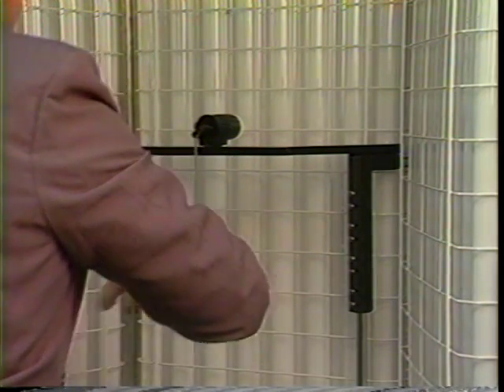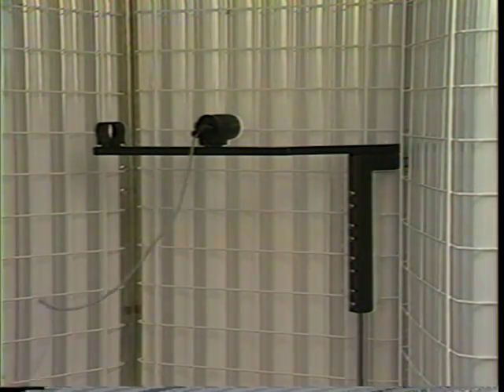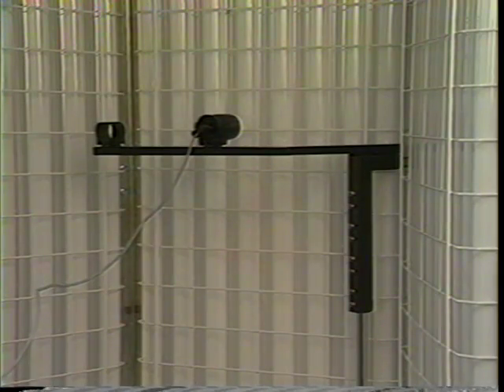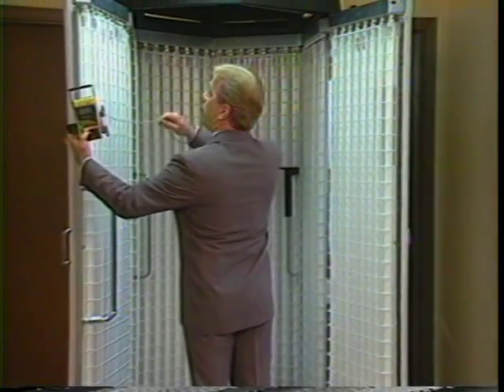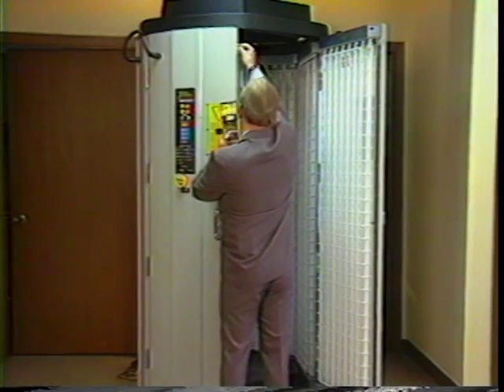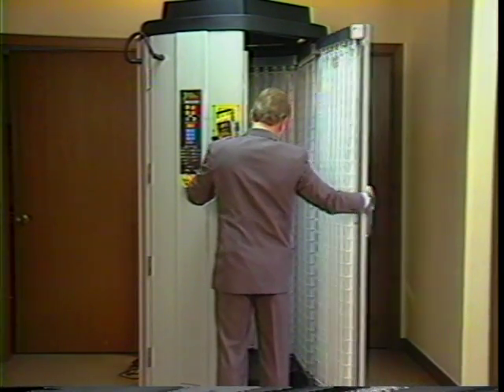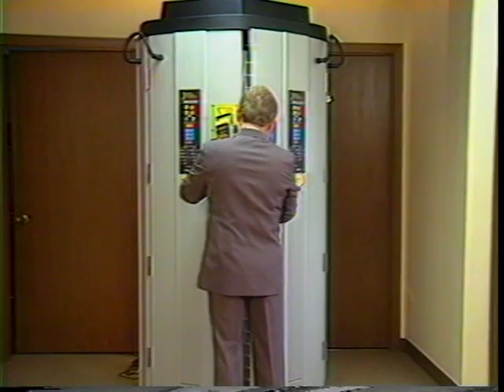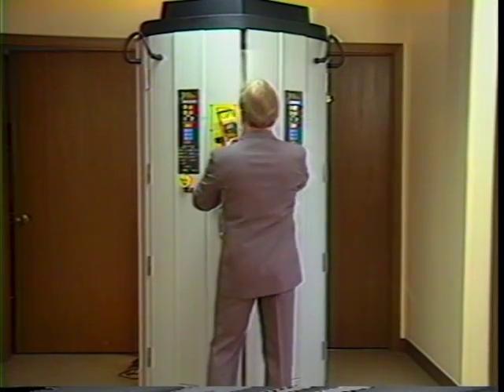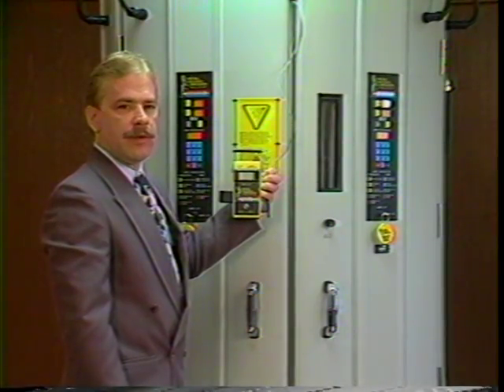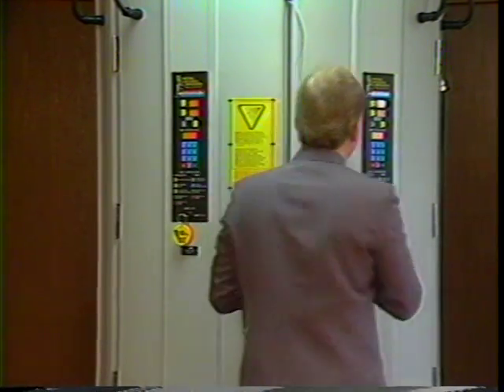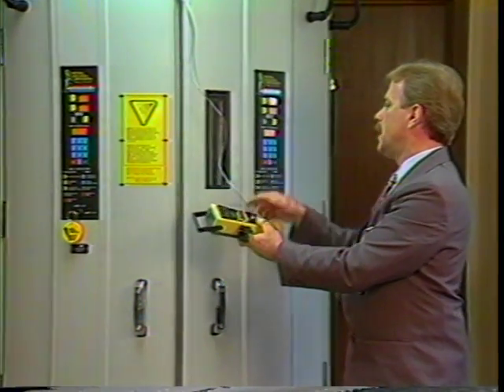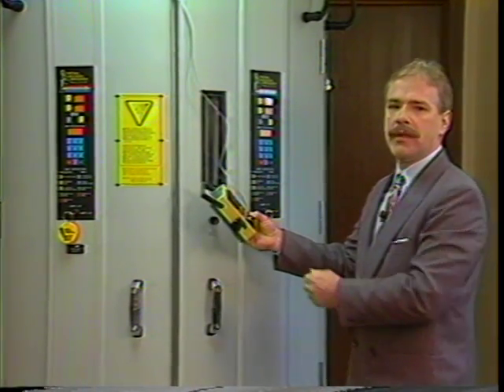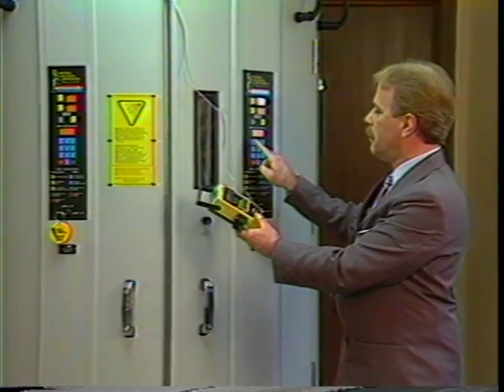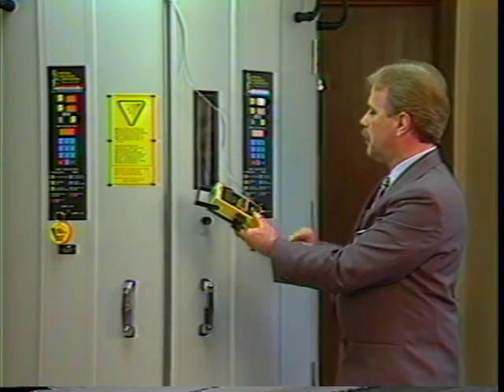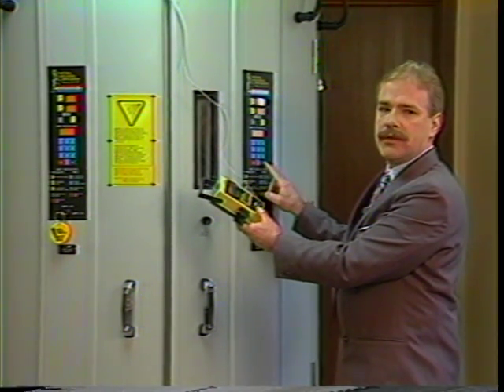Note that you will have to unwind the cord and trail it out of the unit as you step outside and hang the cord over the specially designed slot on the top left door. Then close both doors. To start the unit for UVB measurement, simply depress the gray timer button once again and using the keypad enter 1 minute on the timer by depressing the digit 1 and 0 twice. Then depress the green start button once again to turn the unit on.